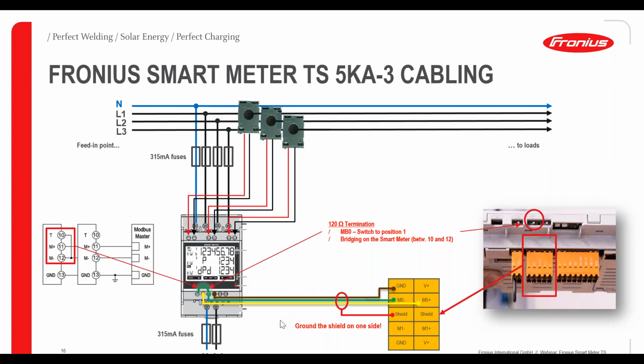Also, something we need to keep in mind is that for this type of smart meter, we need an external power supply underneath here. So we can see the phase and neutral. It could also be a DC power source, but since we are talking about placing the smart meter in the main distribution panel, phase and neutral must be available anyway. Again, here we have fusing of a minimum of 315 milliamps, not mandatory, if required by that country. We have, again, the same connection to the data communication card. So no differences here, of course.